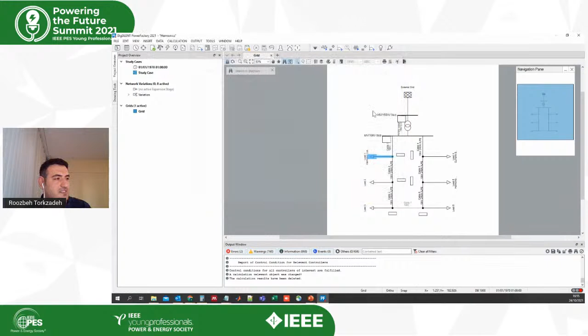Now you can see that for this bus bar, I can see the THD, the total harmonic distortion, and also the HD, which is the harmonic distortion, but for the fifth. If I want to see the value for the seventh order harmonic, we need to click here again, and then put 7 here, or put 350 here. It doesn't matter. You can put either of these two. And then when you run it, you can see that the value has changed to 1.6.